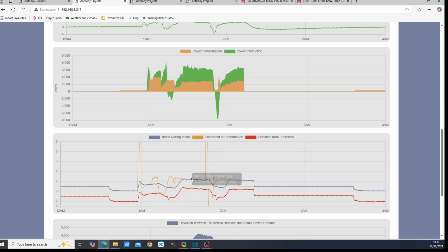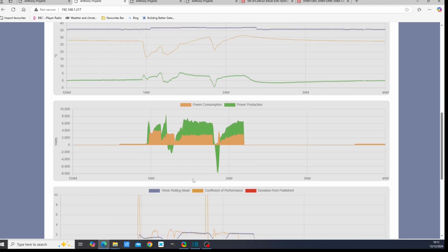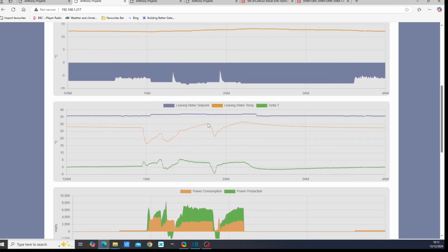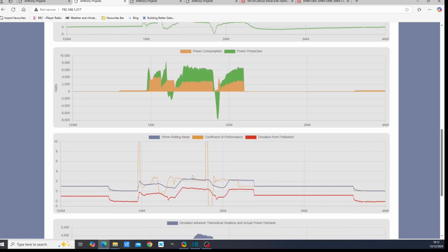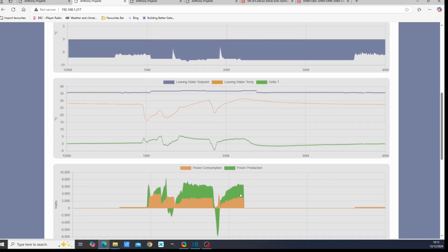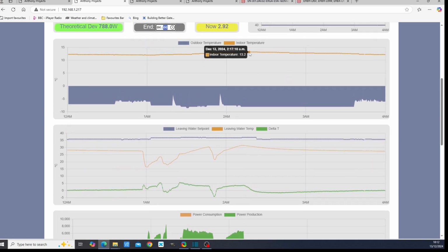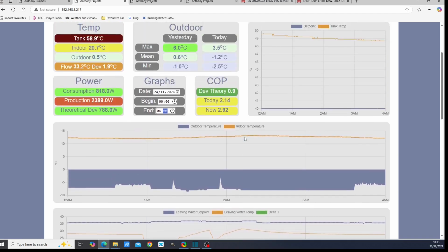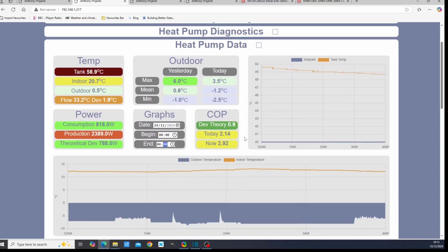So we've got a coefficient of performance of about 2.4. Now the thing is that the higher the leaving water temperature, the lower the coefficient of performance. So we've got a set point of 35 degrees, which we never reach. And as it rises up, the coefficient of performance gradually starts dropping down. Now, it never reaches it because we reached the cutout temperature before we reached the leaving water temperature. So that is the first operating regime.